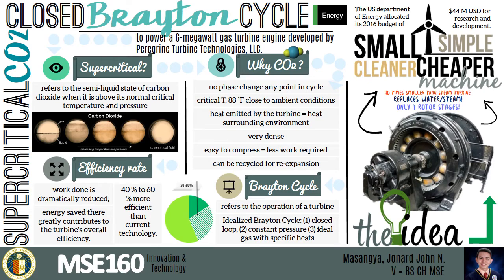The term supercritical describes the state of carbon dioxide above its critical temperature and pressure, in which carbon dioxide exhibits its promising properties. First, it is nearly twice as dense as steam, resulting in a very high power density. Second, it exhibits no phase change at any point of the cycle, hence its state is isolated. Also, it is easier to compress than steam and allows a generator to extract power from a turbine at higher temperatures. That's why it is 40–60% more efficient than current technology, with a net result of a simpler turbine that can be 10 times smaller than its steam equivalent.